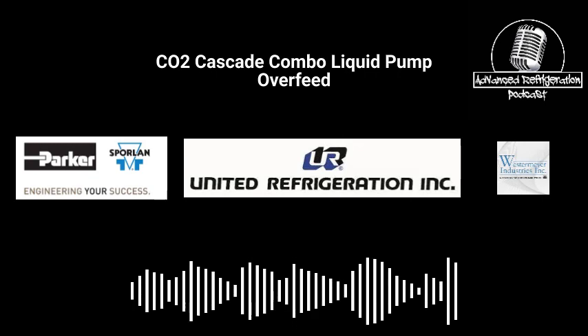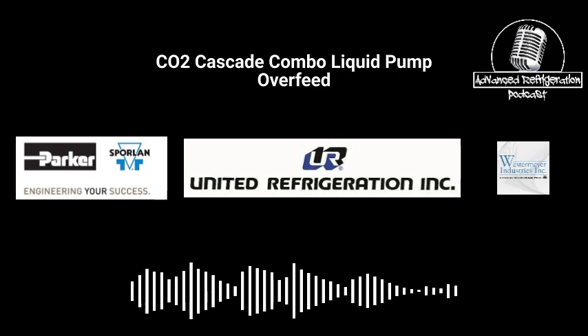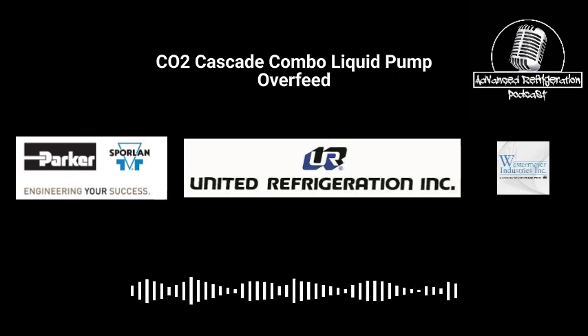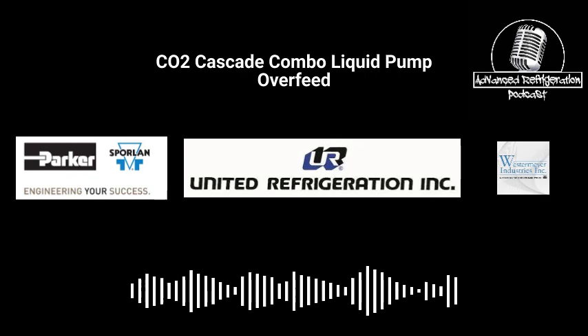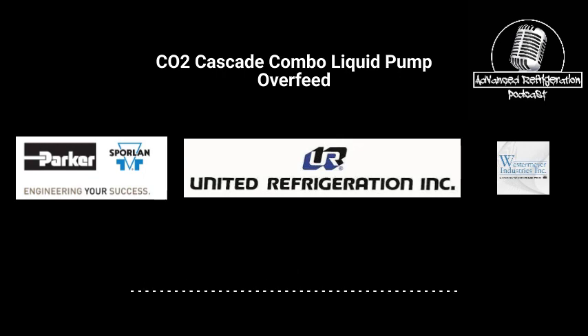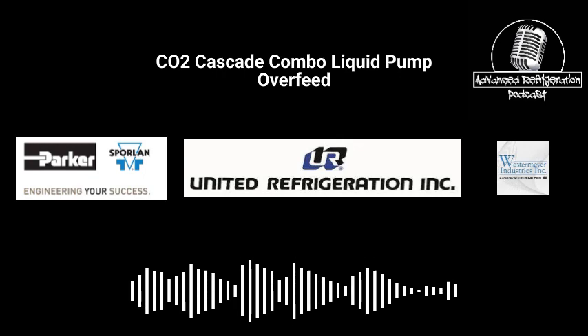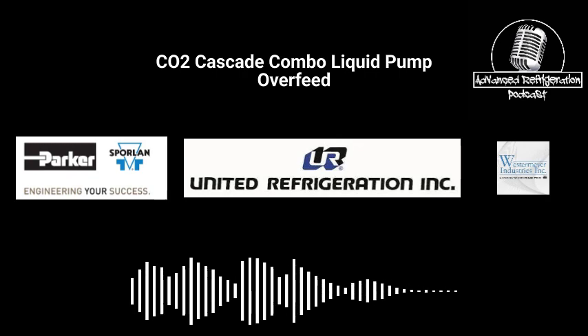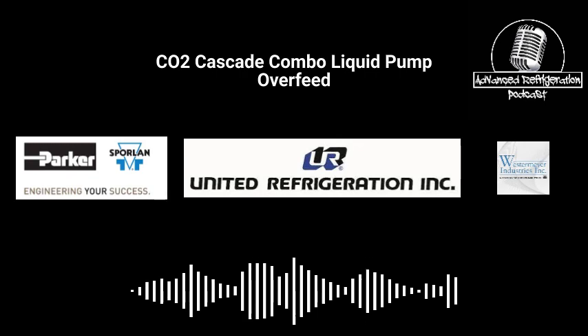I have a question. In the past 4 months, I've read so much different CO2 material. Some manufacturers say they have balancing valves for the liquid pump style overfeed system, so in case your piping isn't directly even, you can modulate that flow a little bit. Have you seen the isolation valves? I haven't seen the isolation valves, but I've seen CDS valves used. Or a balancing valve, it's almost like a circuit setter. It basically does both. You can shut it all the way off, plus it's a balancing valve. And they put it on the CO2. So I wouldn't see why it would be a problem.